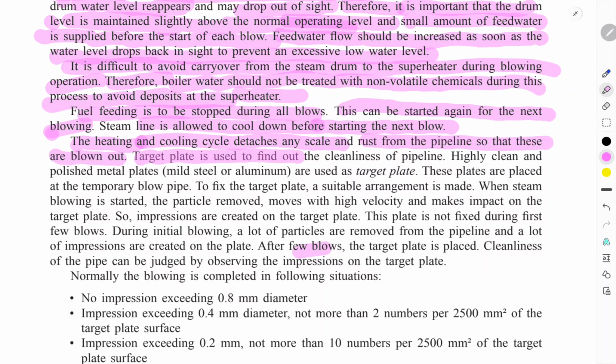The target plate is used to find out the cleanliness of the pipeline. Highly polished metal plates, mild steel or aluminium, are used as target plates, and these plates are placed at the temporary blow pipe with a suitable arrangement made to fix them. When the steam blowing starts, particles move at high velocity and impact the target plate, creating impressions. The plate is not fixed during the first few blowings, since lots of particles are removed from the pipeline initially and a lot of impressions would be created. After a few blowings, the target plate is placed. The cleanliness of the pipeline can be judged by observing the impressions on the target plate.